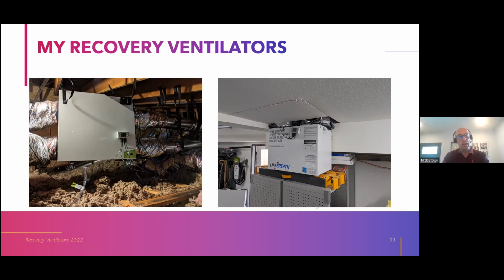Upper right is the exhaust, and lower right is the supply. And then I've got those ducts snaking off to various points in the house, which I'll show you a diagram of in a minute. The one on the right is the one for the new ADU. In its case, all the duct connections are on top, so they're in the drop ceiling above. And then they have a pant leg boot fixture for the outdoor penetration, so that there's just one penetration needed and it splits the air streams, which was pretty clean. Both of them have HOBO monitors to monitor the temperature of the air streams.